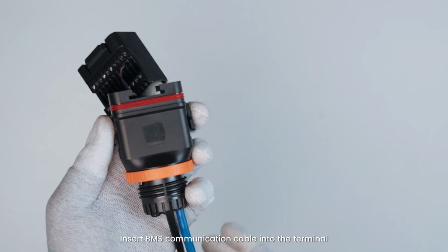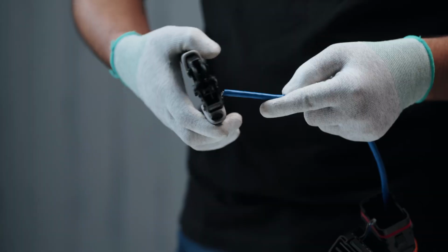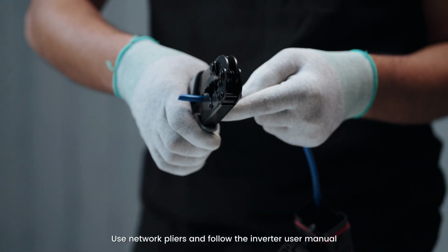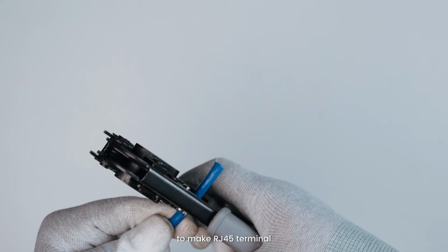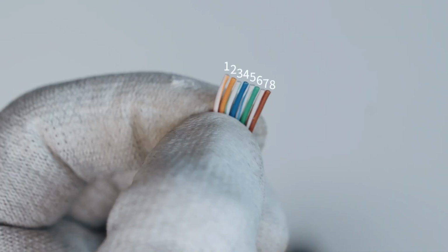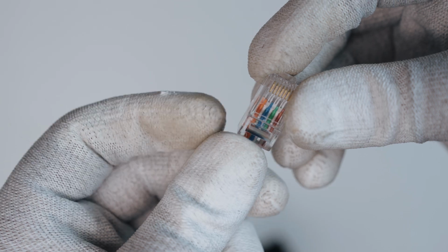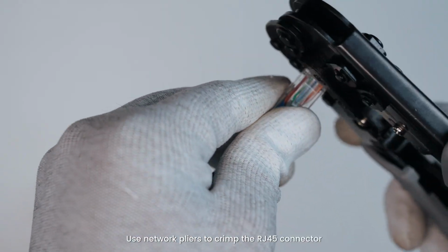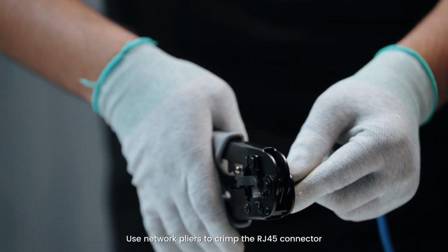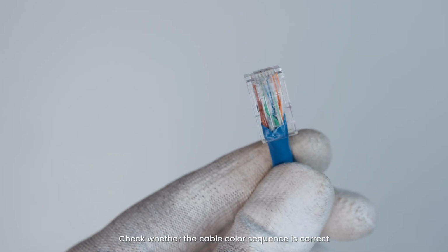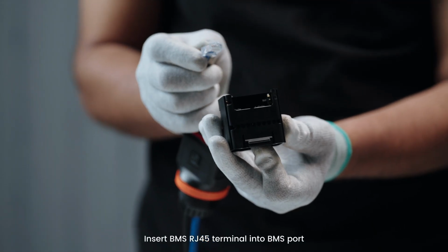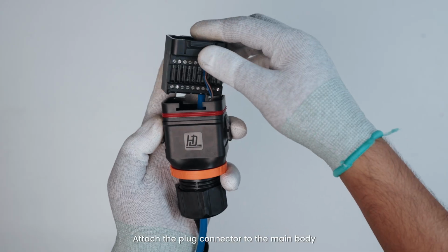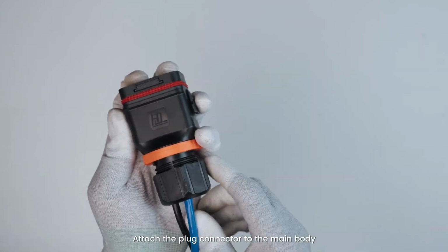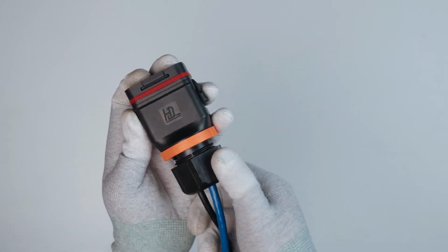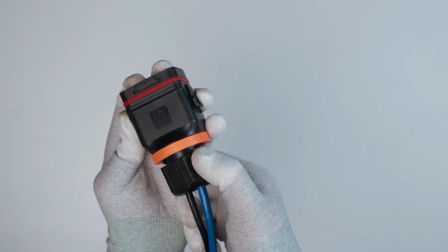Insert BMS communication cable into the terminal. Use network pliers and follow the inverter user manual to make RJ45 terminal. Use network pliers to crimp the RJ45 connector. Check whether the cable color sequence is correct. Insert BMS RJ45 terminal into BMS port. Attach the plug connector to the main body and plug it into the empty hole. Then tighten them.